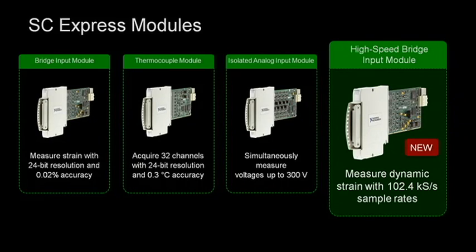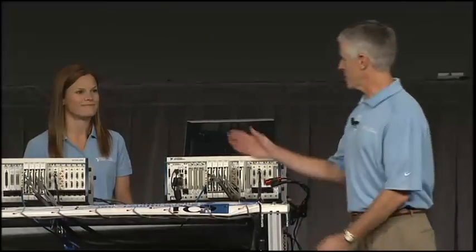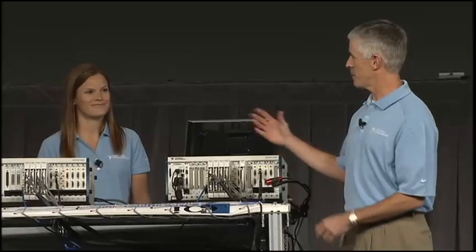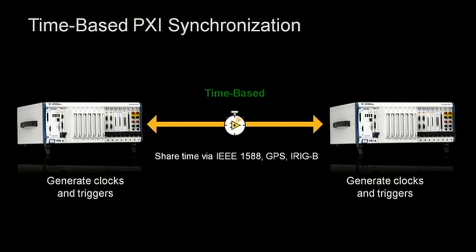To test a full-scale wind turbine blade, we need to measure thousands of strain gauges — that means multiple synchronized chassis. To show how that's done, we split our strain measurements across these two systems. Rather than using coax to synchronize the clocks, we're using PXI clock disciplining in the soon-to-release PXIE 6674T. We're using it to synchronize the 10 MHz clock with time references such as GPS, 1588, or IRIG-B, so we can synchronize the chassis without any physical connection between them.